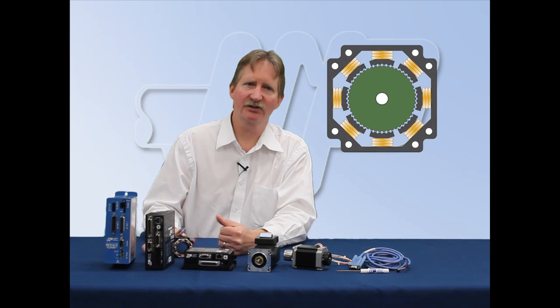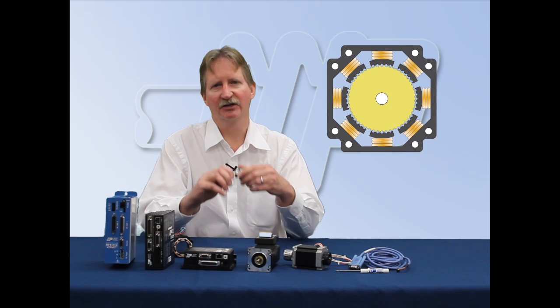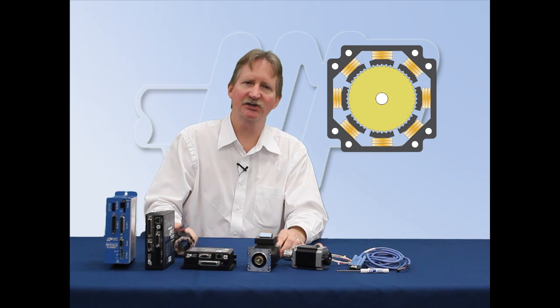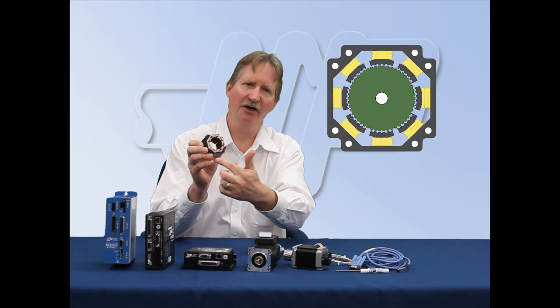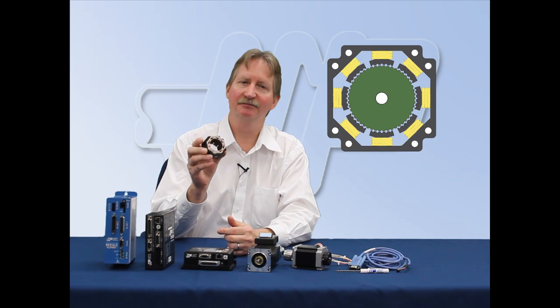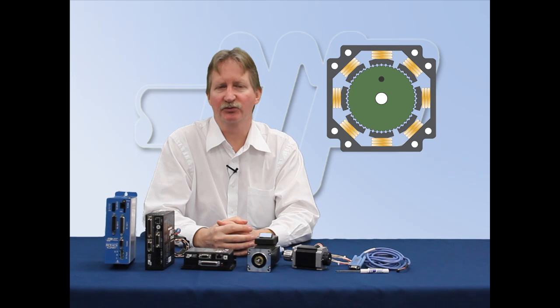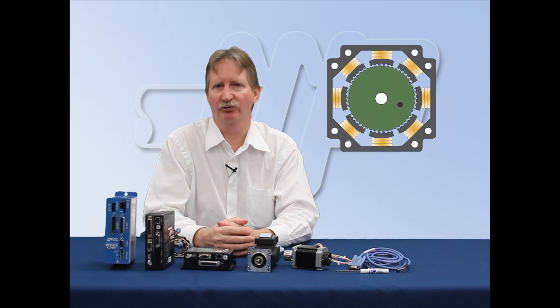At the heart of a step motor is a permanent magnet that rotates on bearings called the rotor. The other critical part is the stator, a series of electromagnets surrounding the rotor. When the drive sends electric current through the stator, the resulting stator field forces the rotor to react.